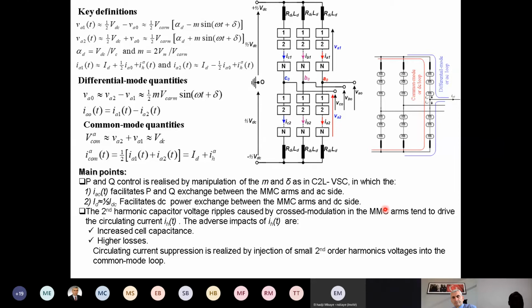And the second harmonic capacitor voltage ripple caused by cross modulations in the MMC arms tends to drive a new current, which we call circulating current, which is this current component we call here H. And the adverse impact of this current is that it increases the ripple in the capacitor. So you will need a bigger capacitor to have lower ripple, which meets the requirement, which is around 10%. This is one of the consequences of that, and it also increases the losses.